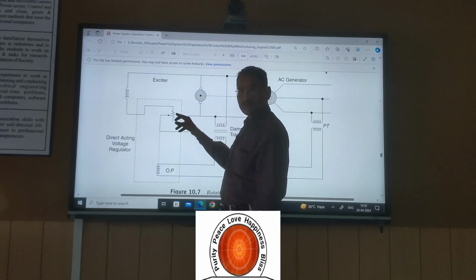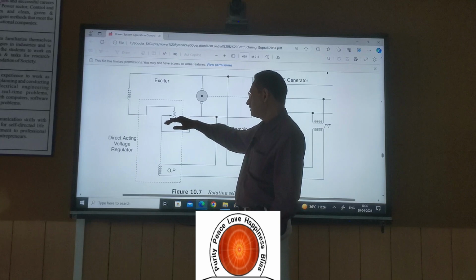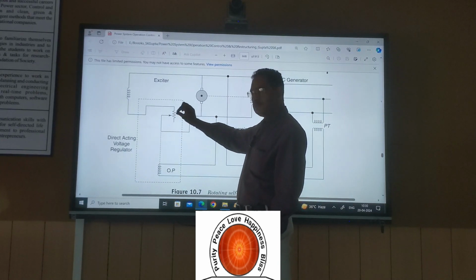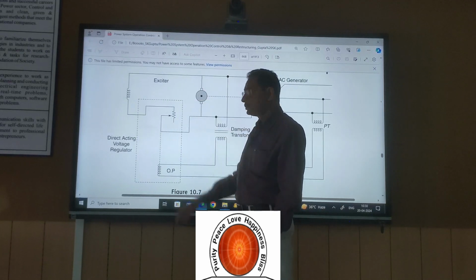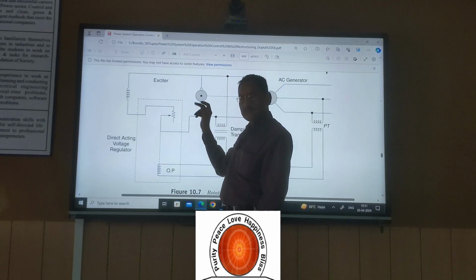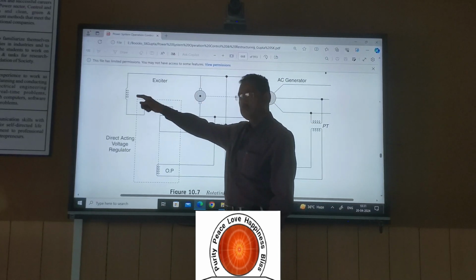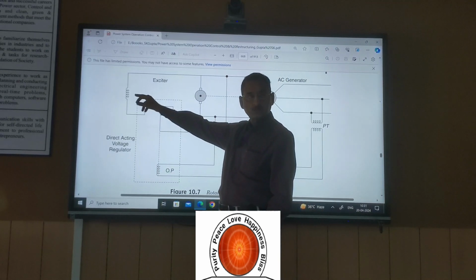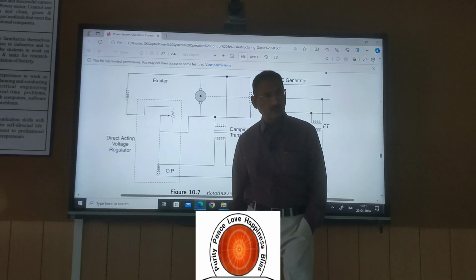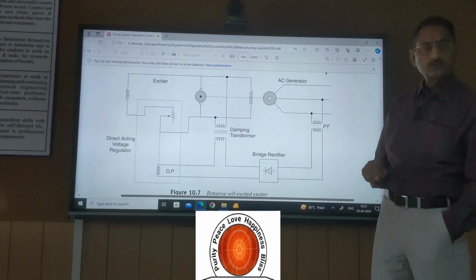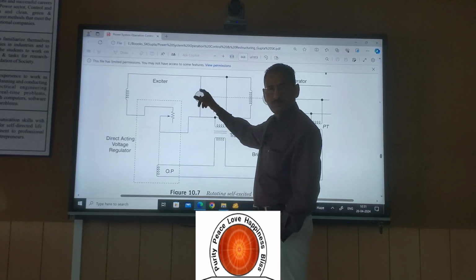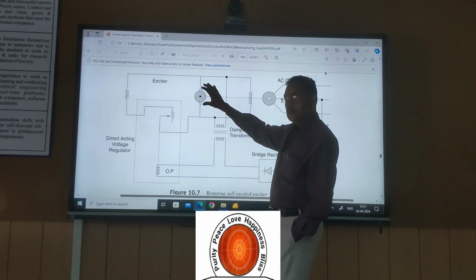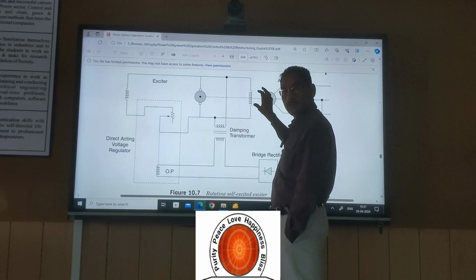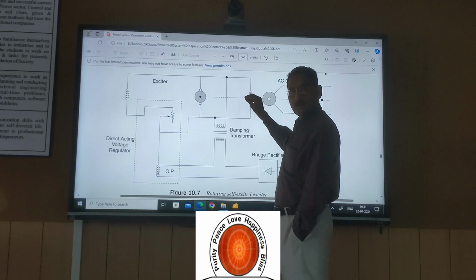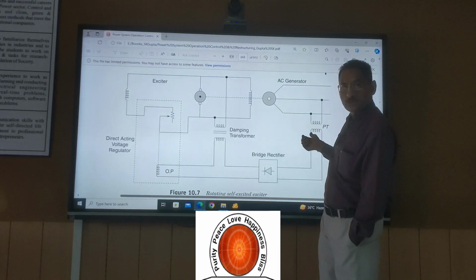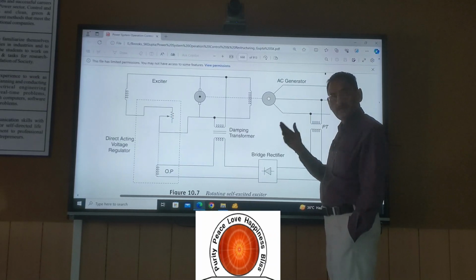And we described what happens if the resistance increases. For example, if you pull this down, the resistance will increase. If the resistance in the excitation increases, the current going to this field will decrease. So when the current of this field decreases, then the voltage V of the DC generator, which is K phi omega, is reduced, because phi is reduced by the increase of resistance and I is reduced. If this voltage is reduced, it will supply less field current to the main generator. So when the field current is reduced, the voltage here will be reduced. If the voltage was higher, it will be reduced again and come to the normal 1 per unit.